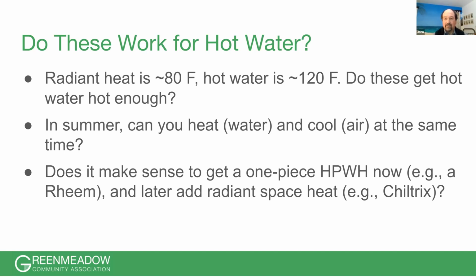Generally speaking, as a designer, we figure that 75% of the water content of your tank is actually usable. So if it's at 120 degrees and it's an 80-gallon tank, that's really only 60 gallons. So how big is the tub? You have to size the tank according to the largest demand, which is going to be the tub, so you might have to have a bigger one. An 80 gallon in a lot of cases covers a lot of our issues - smaller, we could run out of hot water. Then there's always the 119 gallon size as well.